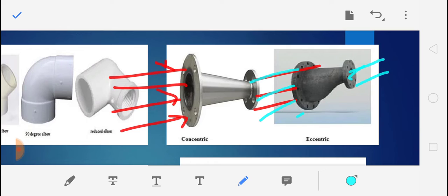A concentric reducer is cone-shaped with a gradual decrease around the pipe, but air accumulation may occur which can result in cavitation. An eccentric reducer has one edge parallel to the connecting pipe, due to which air accumulation is not possible. Therefore the eccentric type is most widely used, and this kind of connection is commonly found in pump houses.